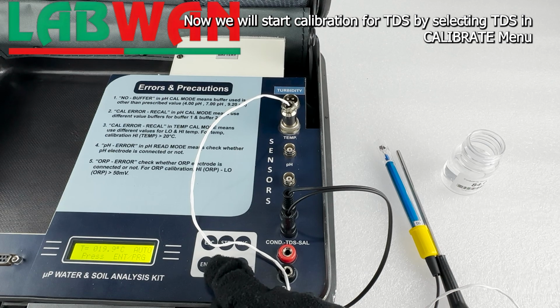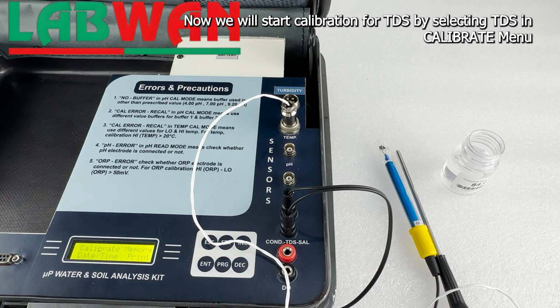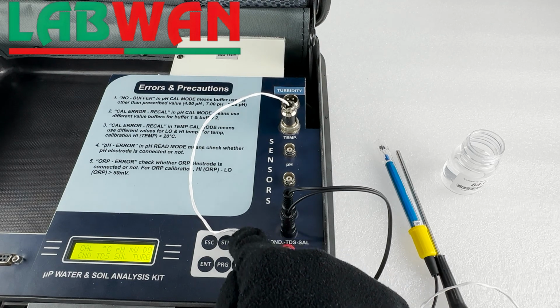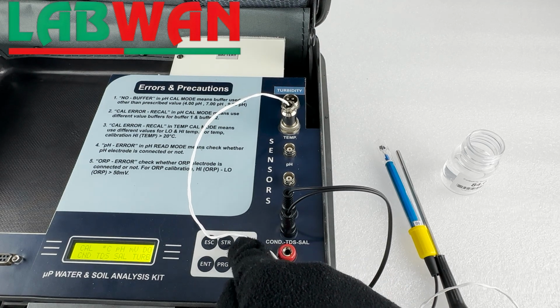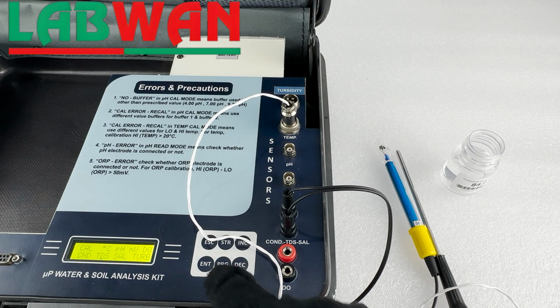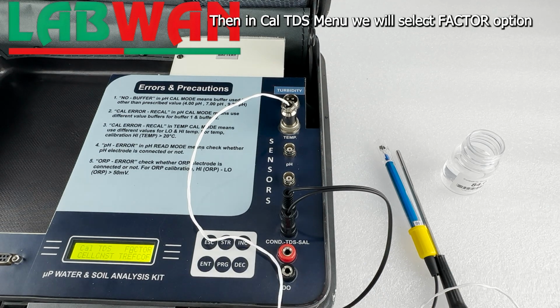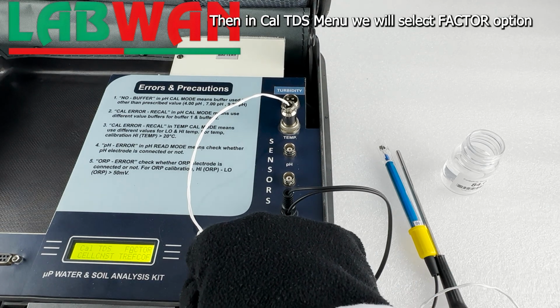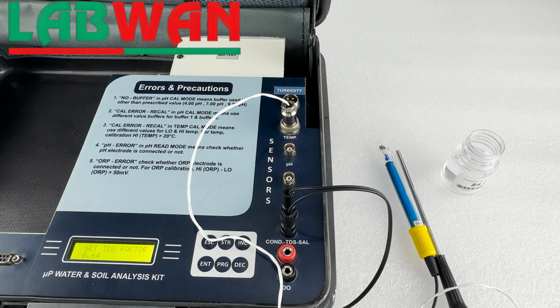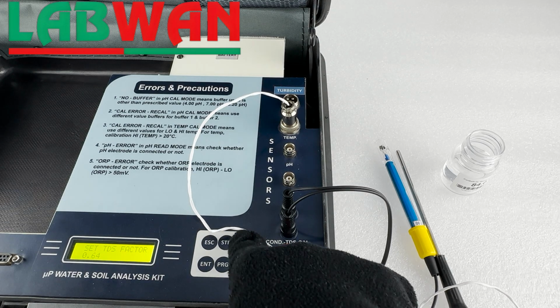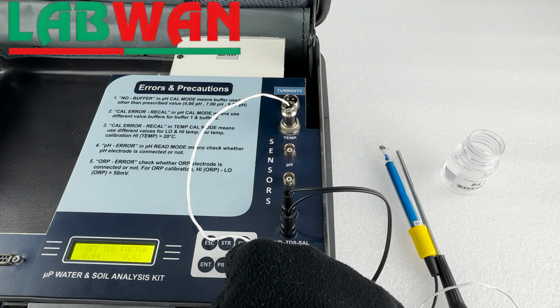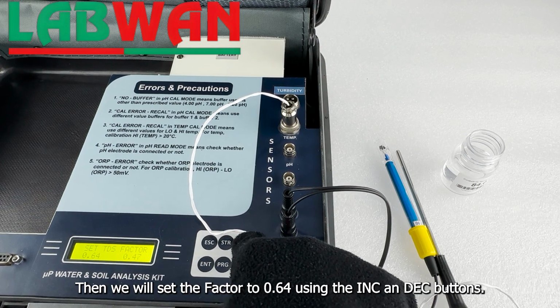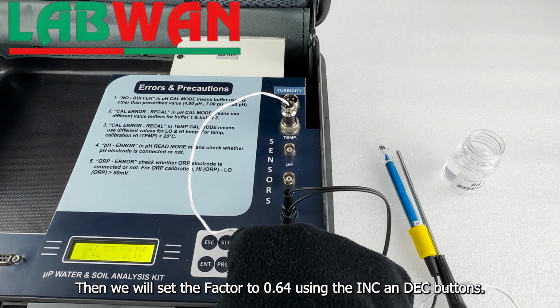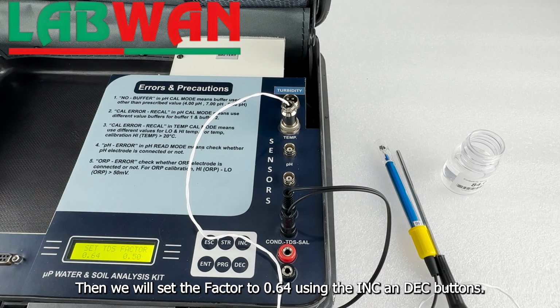Now we will start calibration for TDS by selecting TDS in Calibrate menu. Then in Cal TDS menu we will select Factor option. Then we will set the factor to 0.64 using the INC and DEC buttons.